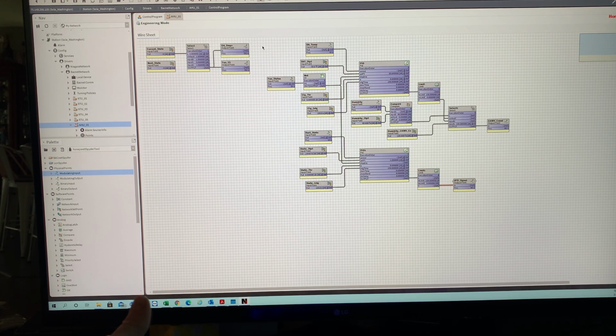Okay, are we sending a signal? Go to the actuator, drive it up and down. Are you getting your 2 to 10, 0 to 10, or 4 to 20 signal to the actuator to move it up and down? If you're not getting your signal, go to the controller itself, take the wire off, and test the output to see what it's doing.